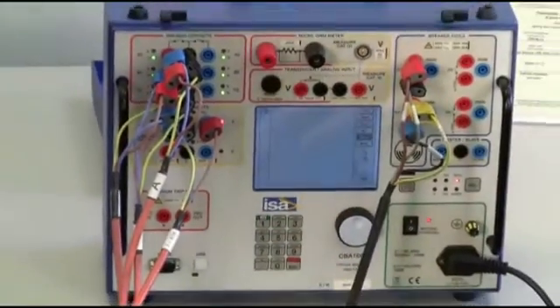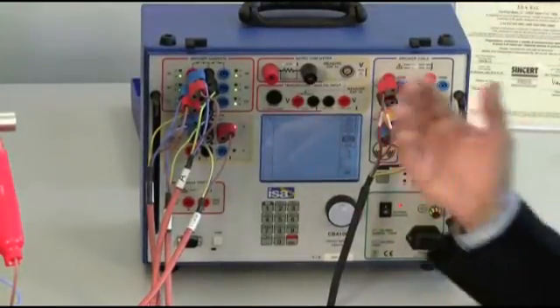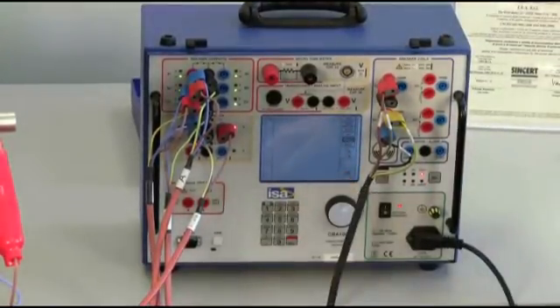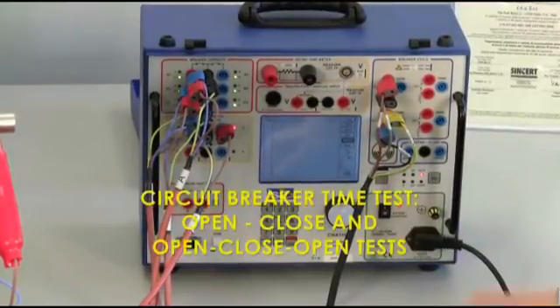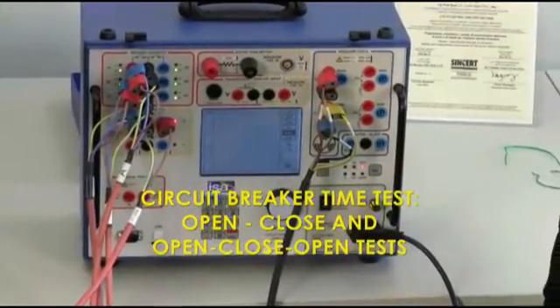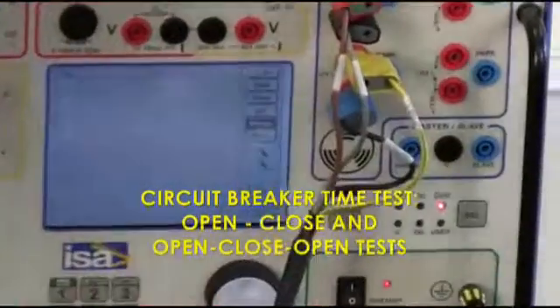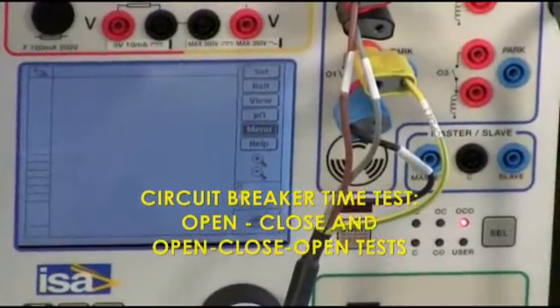And what do I want to do? The circuit breaker is open. So, the first operation will be close it. And I can record the timing during the close. And next, I will go to open, close, open. That is the most severe sequence that the circuit breaker must withstand.